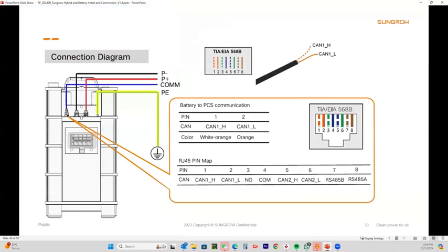Okay, connecting the battery could not be simpler. You get basically positive and negative power cables. Use your normal 6mm PV cable for that, that's fine. There's a communication cable in the box. It's terminated at one end with an RJ45 with a lockable boot on it, and the other end is just terminated like this. On the systems we use the 568B configuration, which means you're using pin 1 and pin 2, which is CAN high and CAN low, which is white-orange and orange. That is the only 2 you're going to use.